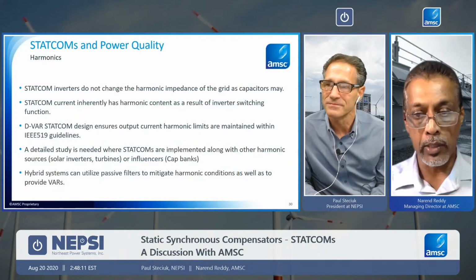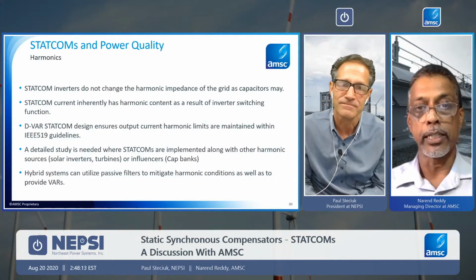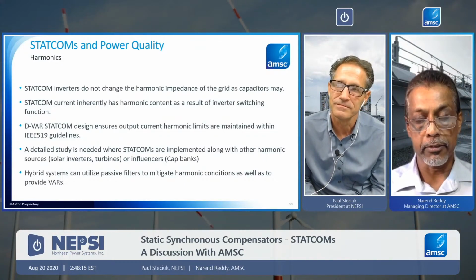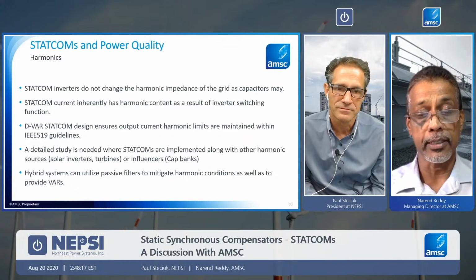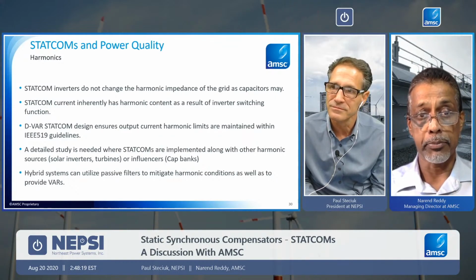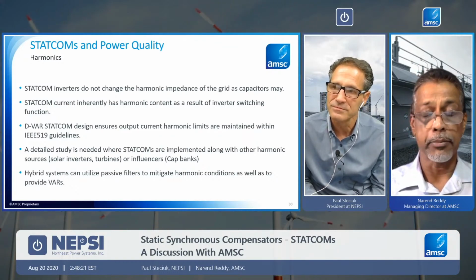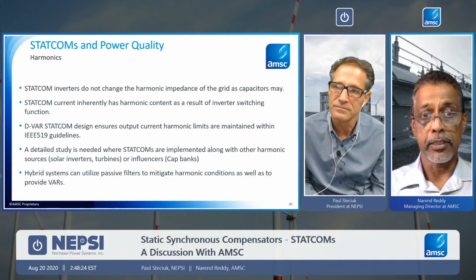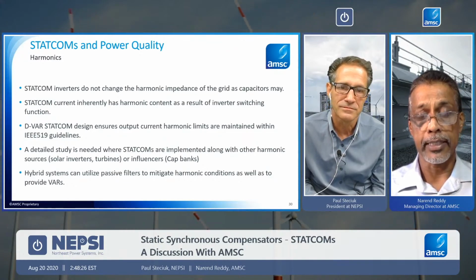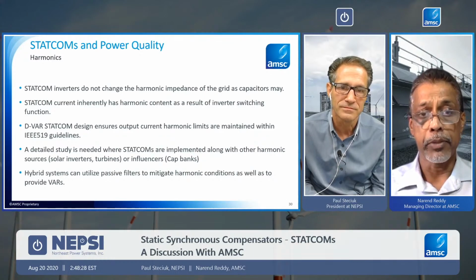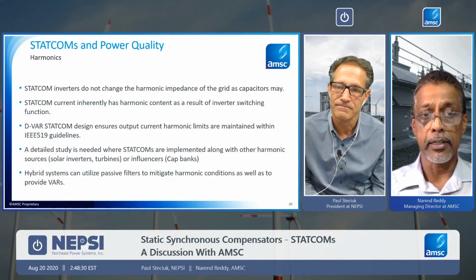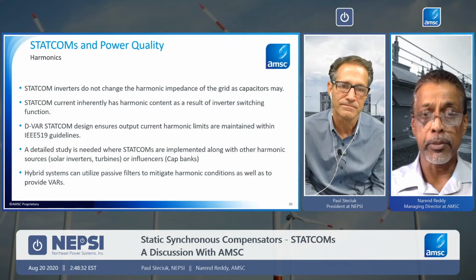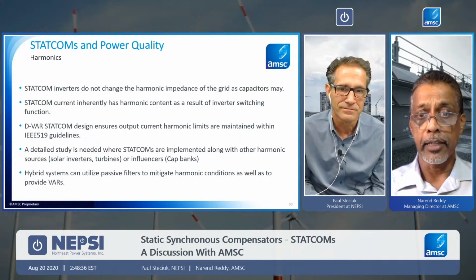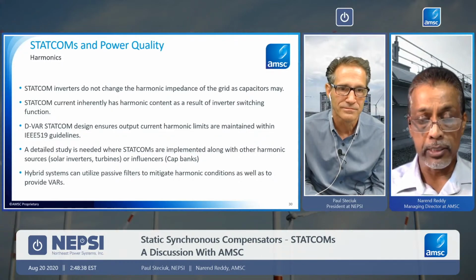Good question. So the STATCOMs and power quality. There are different ways that we define power quality, flicker as well as harmonics and things like that. And I know NEPSI gets into the harmonics part of the grid in terms of providing filter banks. But you're right.